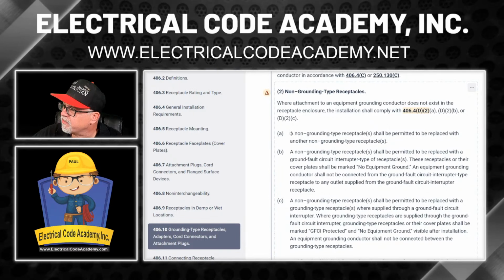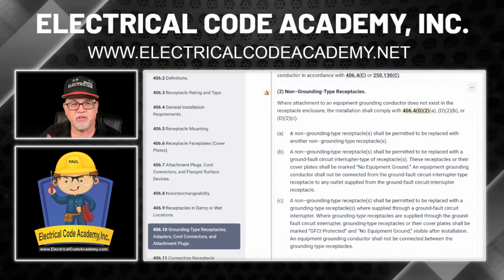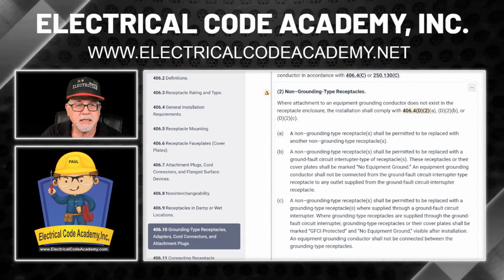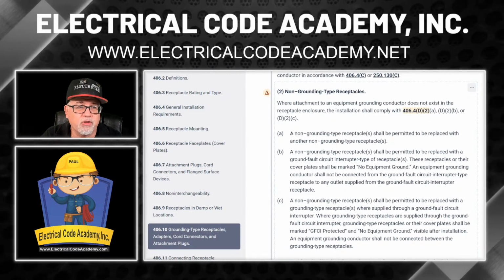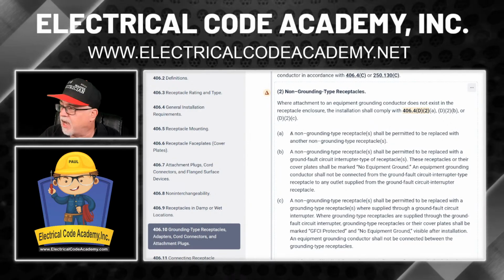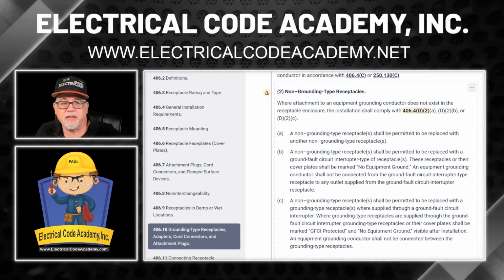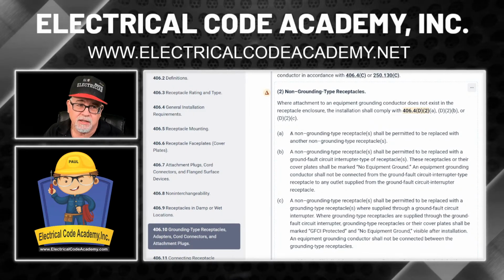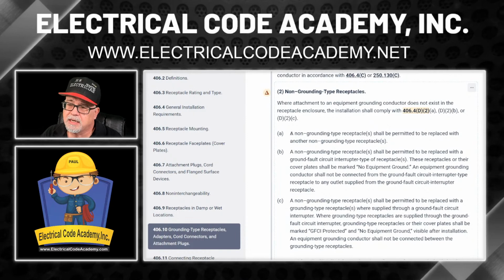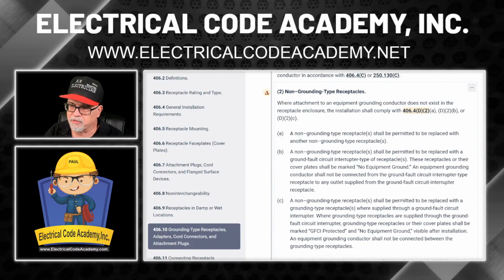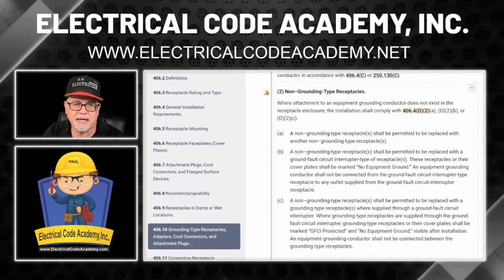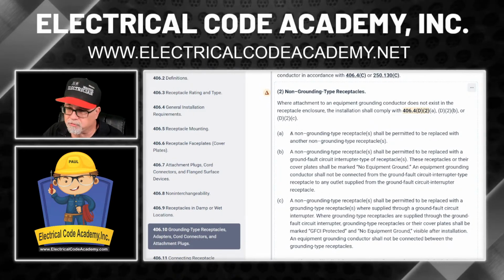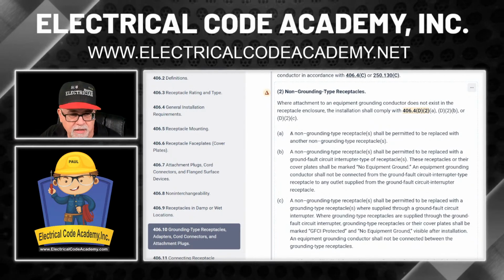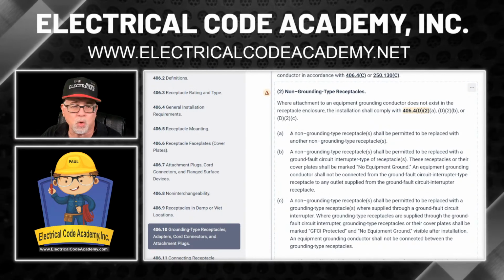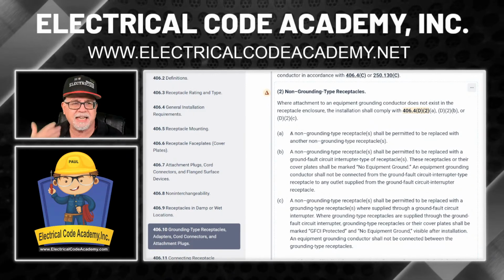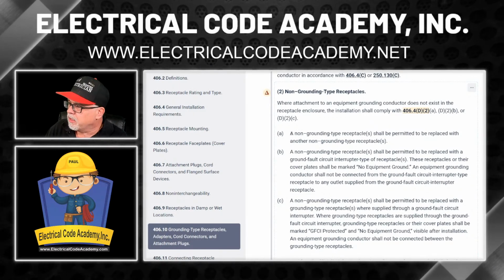Now, the first thing that you could have done if you're a service electrician and you're just going out to a job and you have a damaged 2-prong receptacle is you could simply replace that 2-prong with another 2-prong, okay? A non-grounded type. The code allows for that. It was okay at the time it was originally installed, so I'm going to allow you to put it back the way it was. But people want the 3 prongs for convenience, plugging in things. They want it. But we don't have an equipment ground there. Now, granted, you could rewire it and run brand new branch circuits and add equipment grounds, and you could follow some rules in 250.130 that would allow you to get an equipment ground there. But you're not doing that.